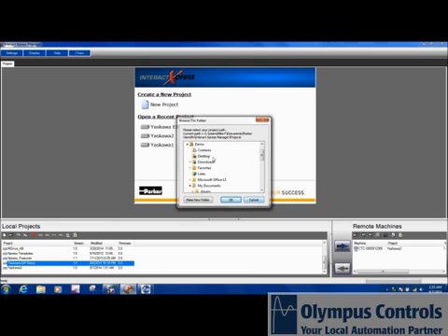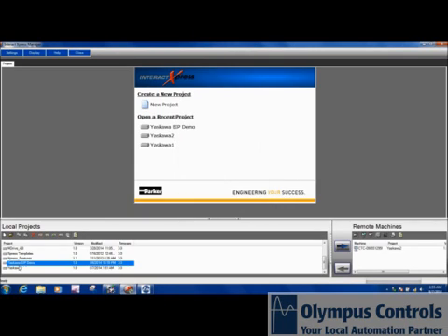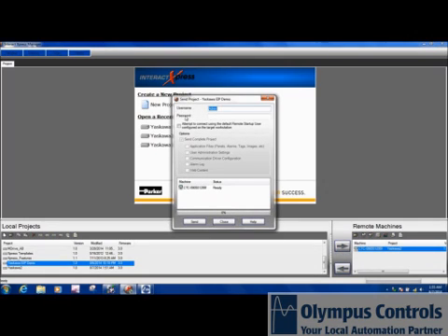Once you see it listed, then you simply highlight it and then highlight the InteractXpress panel that's out on the network, and then click the send button, and you'd want to type in your username of admin, blank password, and then send complete project. Hit send and say yes to all. Now it'll transfer that Yaskawa Ethernet IP demo project over to the touch screen. It'll reboot itself and then be ready to run.